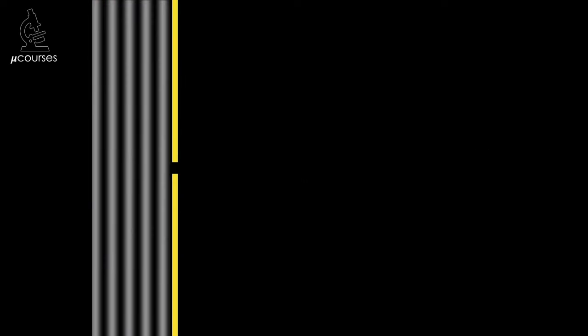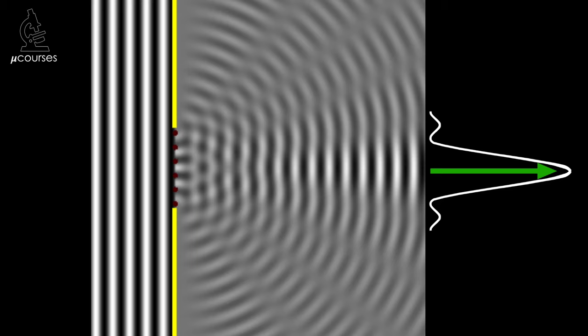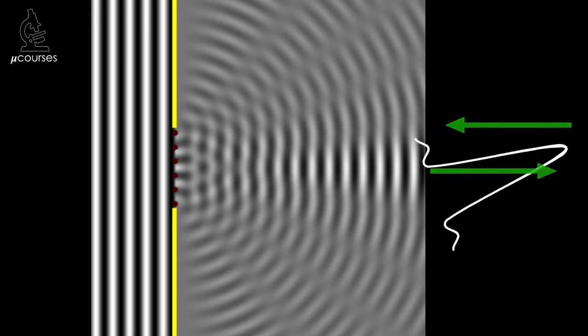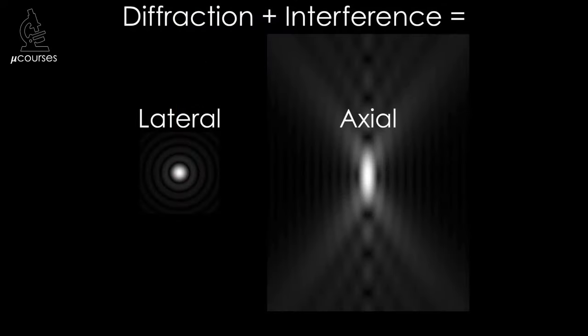Now we finally get back to the microscope. In the microscope we don't have two slits, but there is an aperture in the back of the objective lens, and diffraction occurs there. The aperture in the back of the objective lens is larger than the wavelength of light, so multiple spherical wavelets pass through. If we look at the amplitude of this interference pattern, we'll see that there is a bright central maxima surrounded by dark and light concentric rings — which is our point spread function. So in summary, when we image a point source of light with a microscope, the light we collect from the point source diffracts as it passes through the back aperture of the objective lens, resulting in a three-dimensional interference pattern that we call the point spread function.